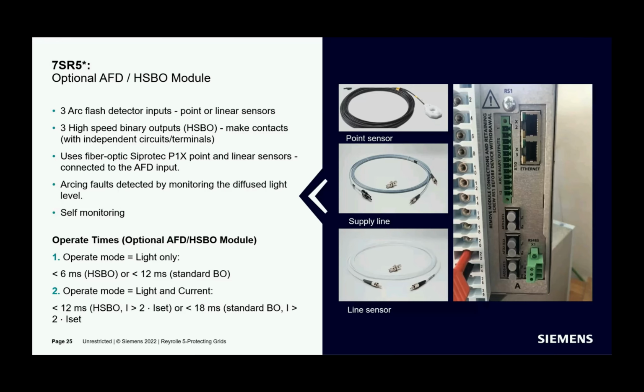The optional, what I call AFD. The optional AFD module provides 3 arc flash detector inputs, which can be connected to point type or linear type sensors. The module comes with 3 high-speed normally open binary outputs as standard. These outputs are independent from each other for maximum flexibility in the circuit design. Actually, all binary inputs and almost all binary outputs are independent from each other when it comes to 7SR5. The module provides a separate self-monitoring feature as well. So this gives an output indication in the event of a failure, which is quite unlikely, hopefully.